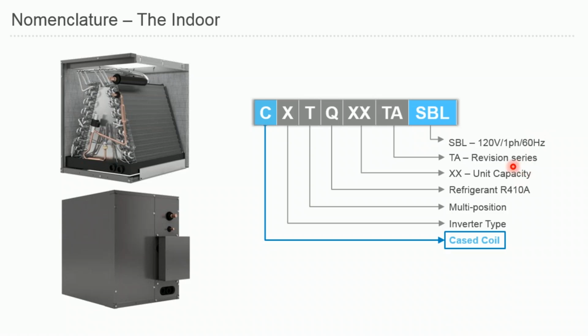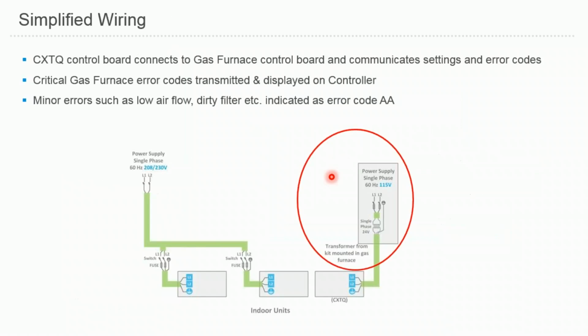It's different than your typical VRV indoor unit. So you don't need to bring a separate power supply for your CXTQ. It is powered by your gas furnace, actually. So when you order a CXTQ A-coil, the unit comes with a transformer kit. This transformer kit is attached to the gas furnace, your Daikin gas furnace you're using in combination with your CXTQ there. The gas furnace is powered by single phase 115 volt power, and when you use that transformer, you're bringing that 115 volt down to 24 volt, which is powering your CXTQ A-coil there.